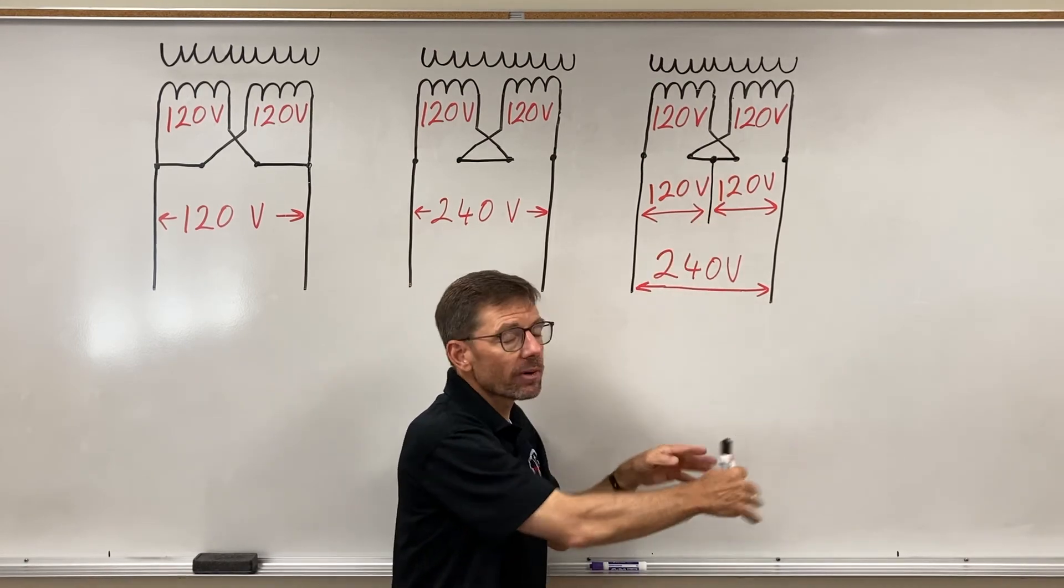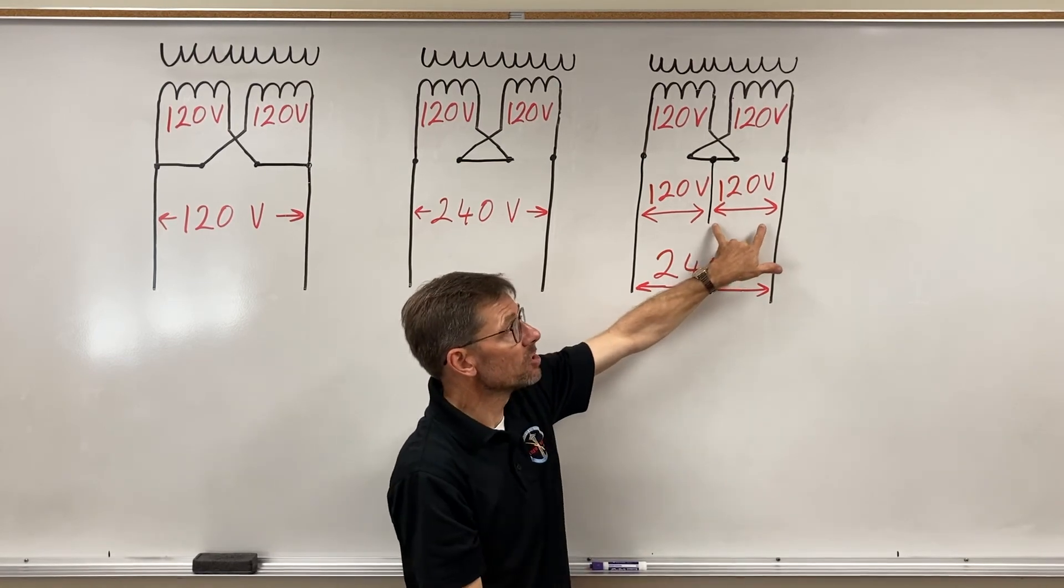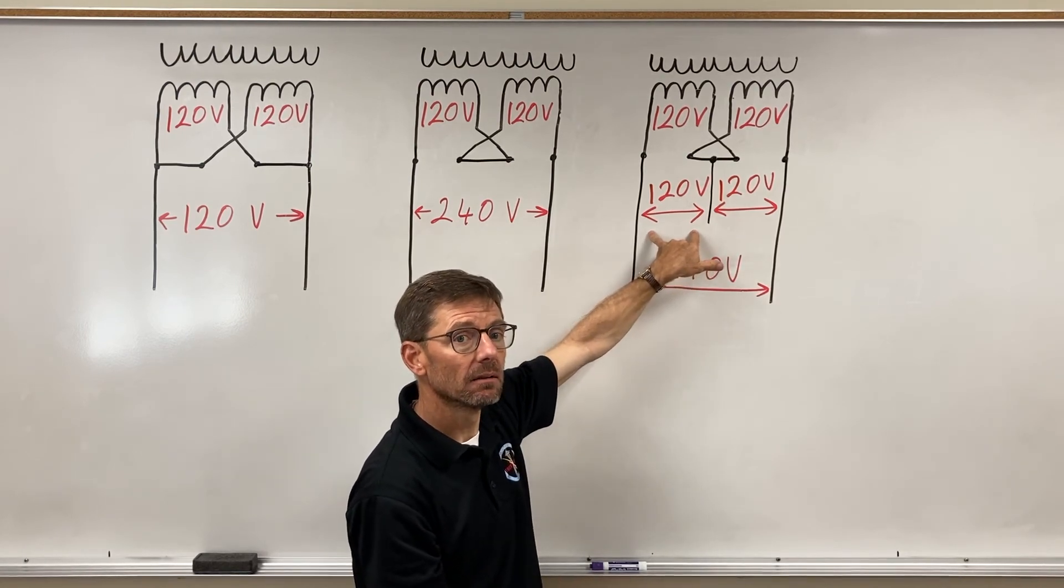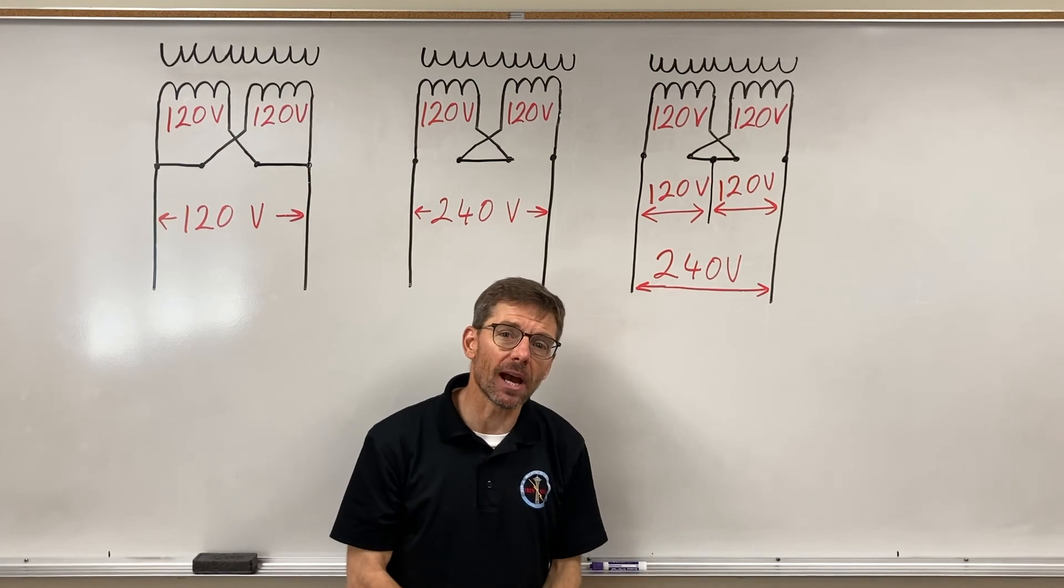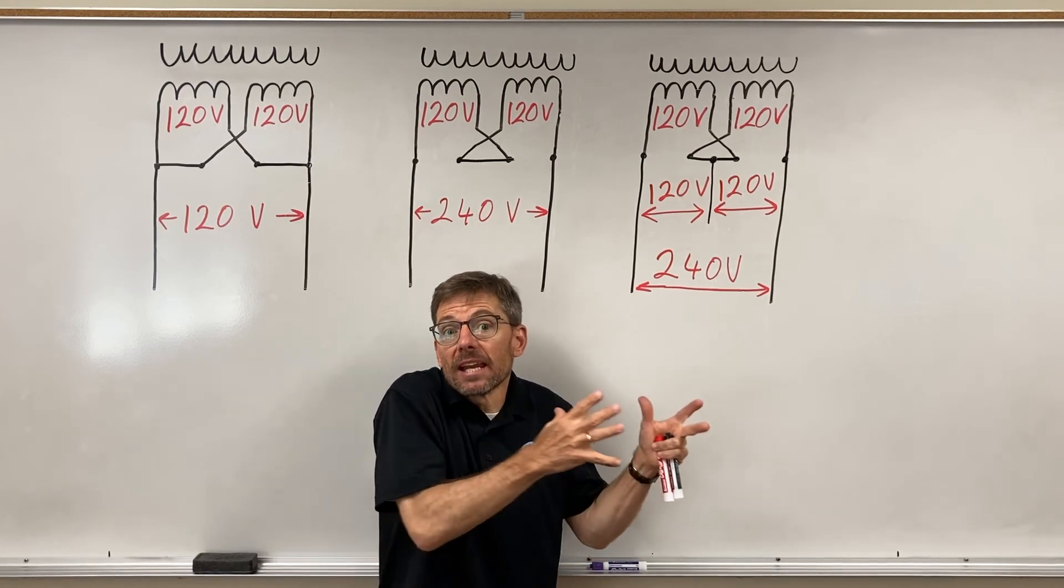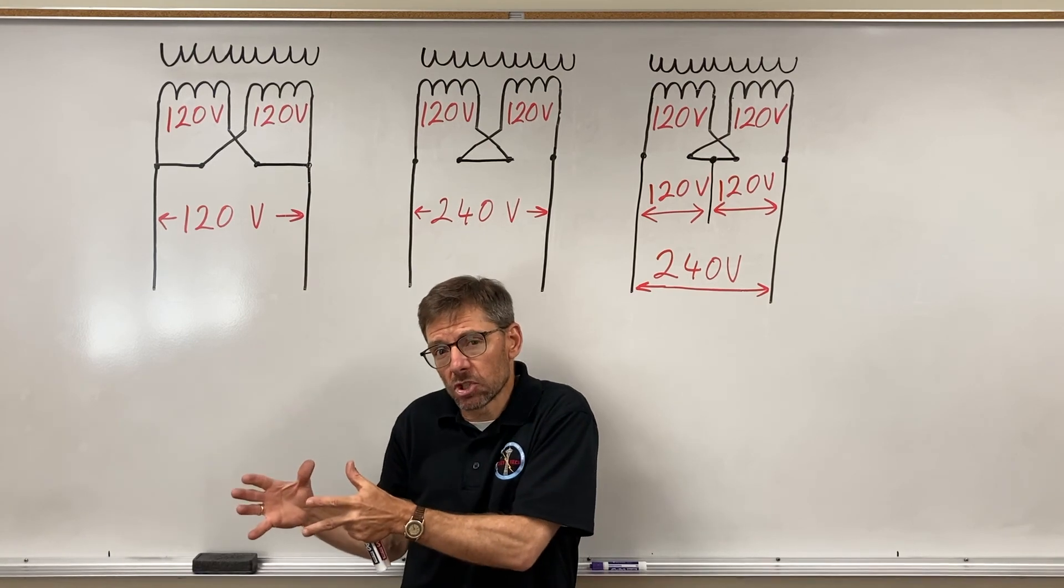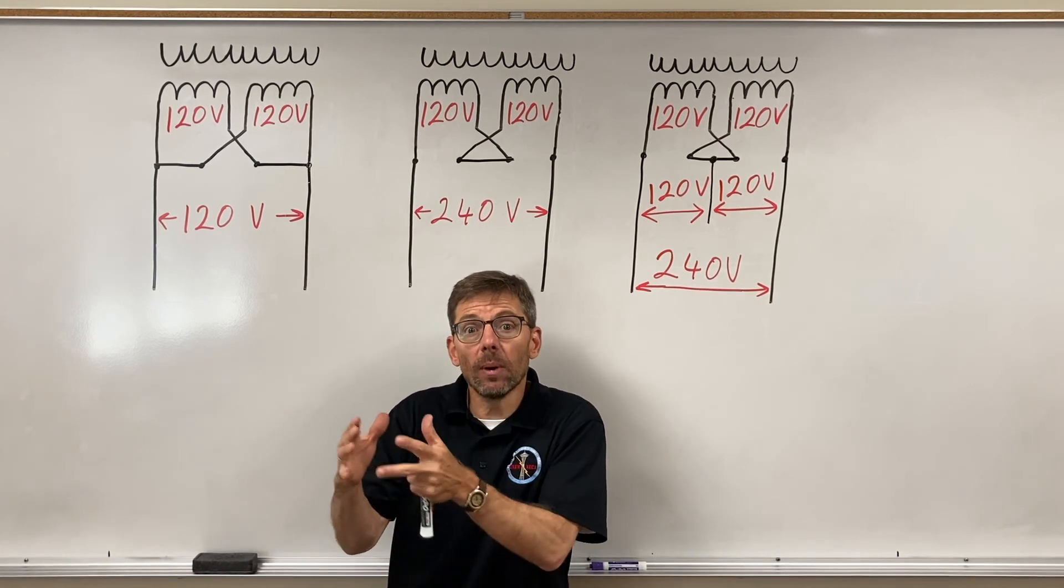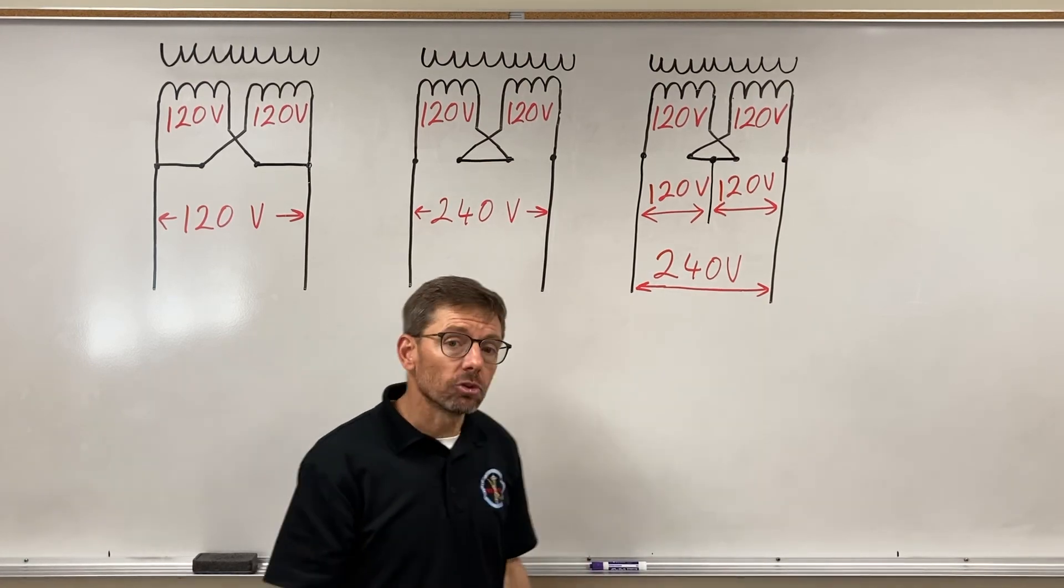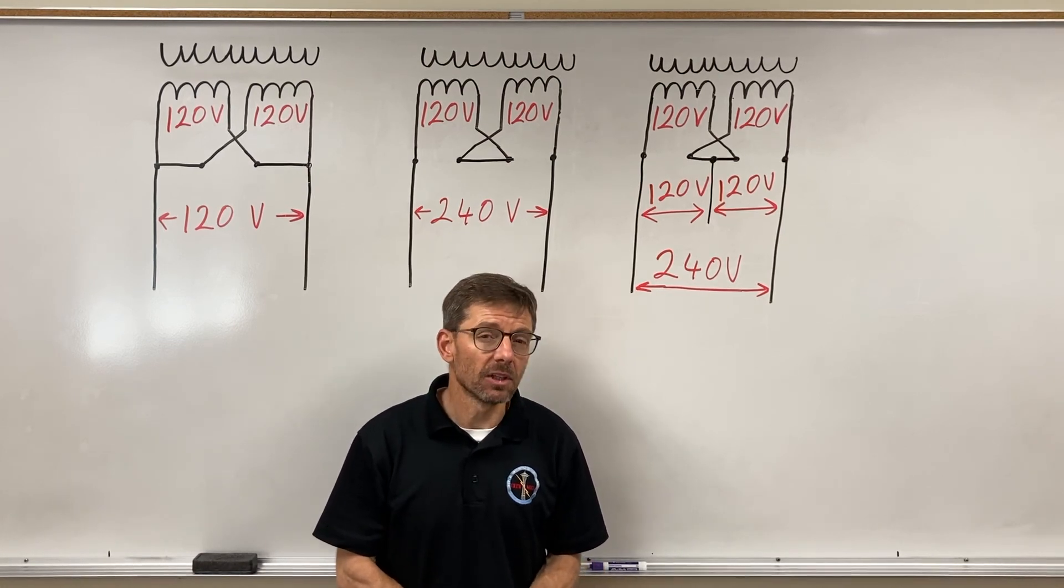So now I'm going out with three wires. If I go between these two I have 240 volts. Between these two 120 and between these two 120. Very similar to what you have in your house. We'll have another video on that, so you can see how the voltage in a freestanding house in the U.S. is different than a lot of our commercial voltages that are 120, 208. No 208 here, that's going to come with a three-phase system. Another video for that one.